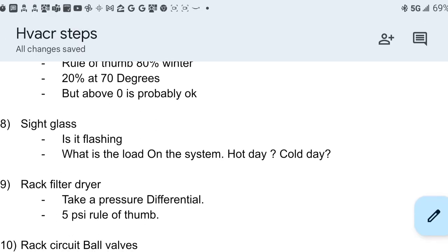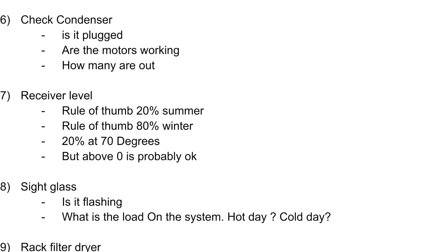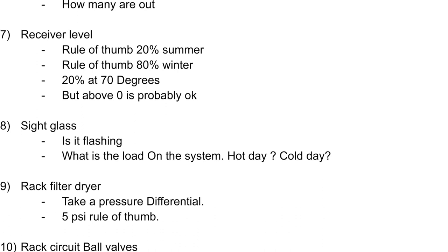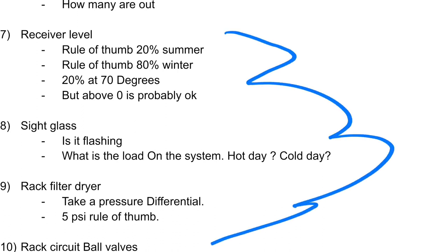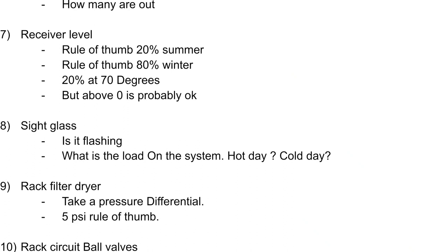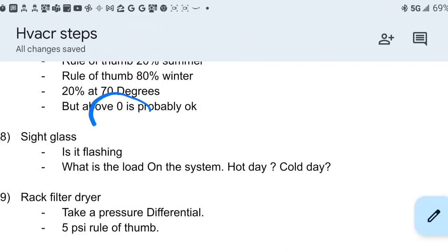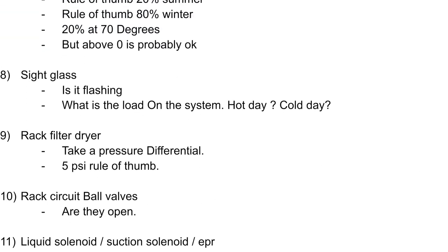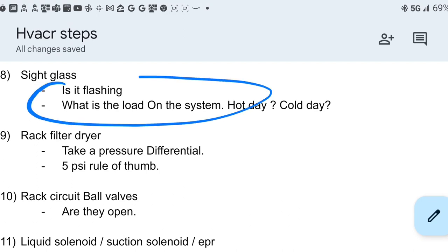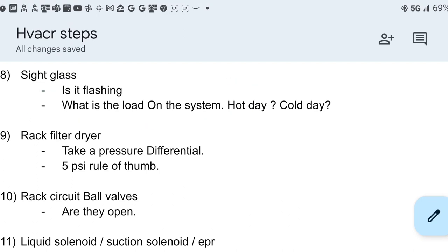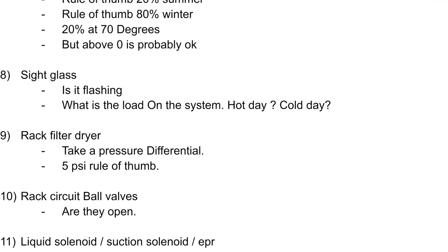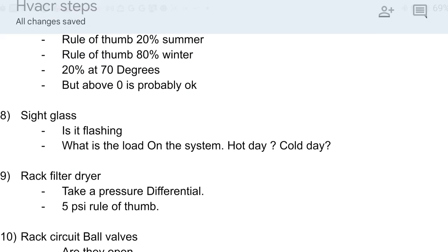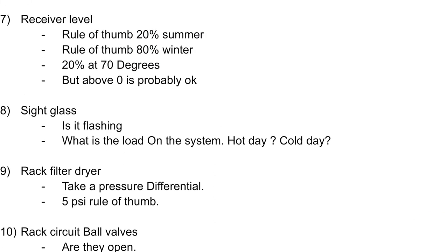Now, next up is your rack filter dryer. This is part of that whole trifecta. These three are all meant to be put together and thought of together as you're checking. For instance, if you have a receiver level of, let's say, 50%, a big receiver level, and your sight glass is flashing, then there's a probability that your rack filter dryer might be clogged.